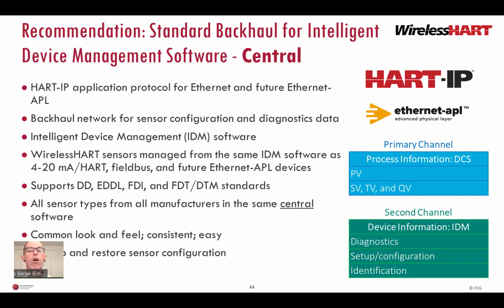WirelessHART solves this with the HART IP application protocol over Ethernet. HART IP is used for the backhaul network to bring sensor configuration and advanced diagnostics data into the plant's existing IDM software without any data mapping, thus saving time. HART IP preserves the message format and data structures for all information in the sensors. This is critical to make EDDL and FDI work. That is transparent integration. That means that all kinds of WirelessHART sensors from multiple vendors can be configured and commissioned from the same single software. The result is a common look and feel across all sensors, so they work the same way with very consistent procedures and therefore are easy to use.